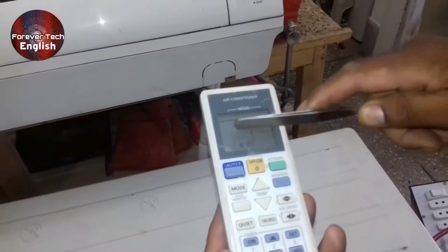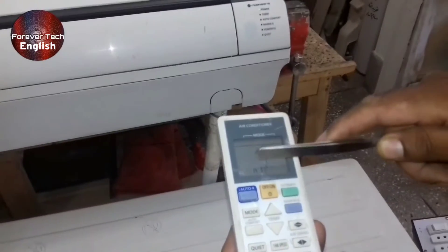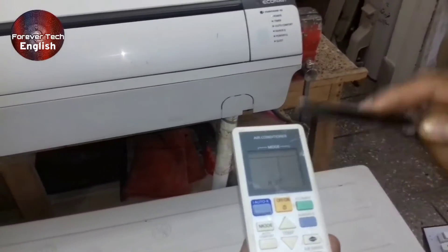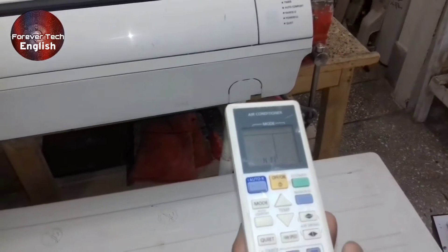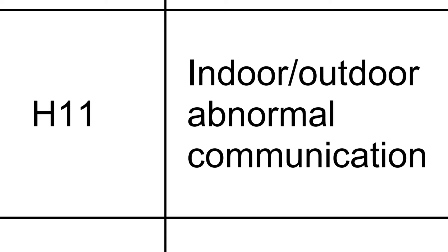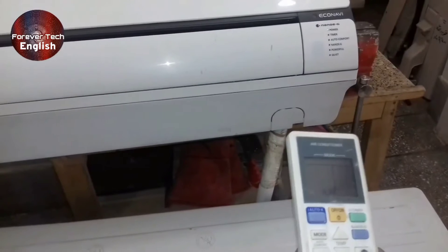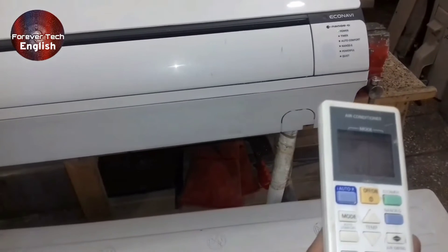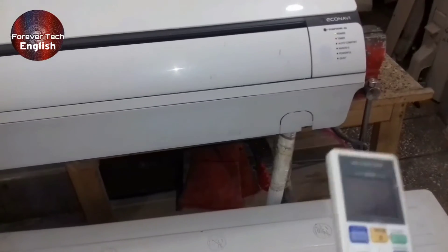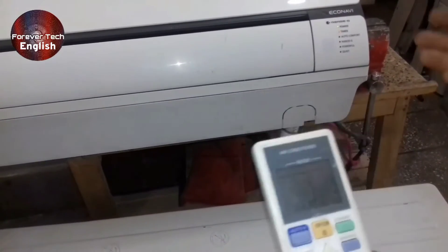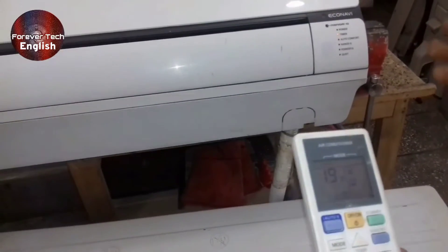When the H11 error code is shown on the display of the Panasonic Inverter Mini Split Air Conditioner, in a technical sense it is known as a communication fault. In a normal sense, it means when the indoor unit is not able to talk with the outdoor, or not able to understand each other's language.